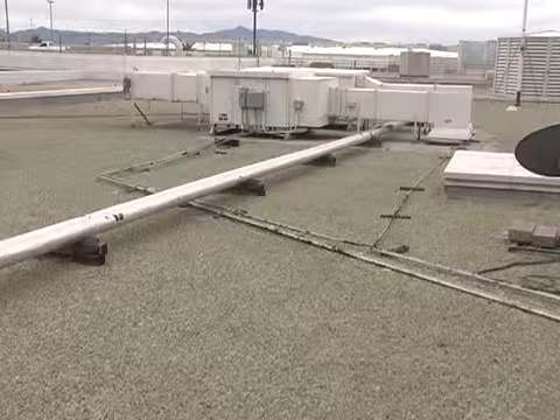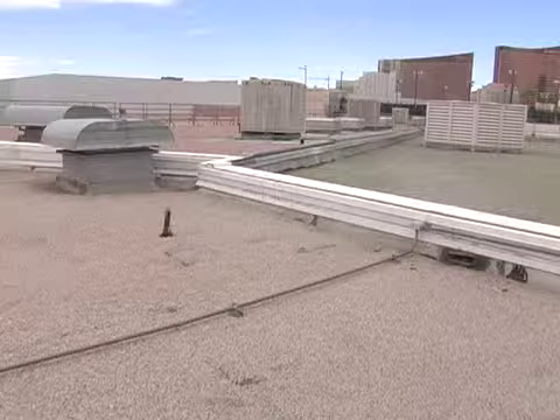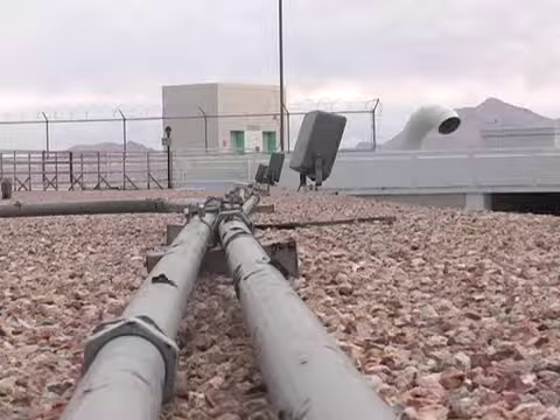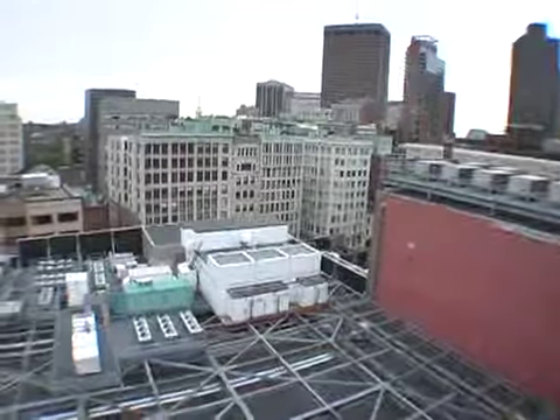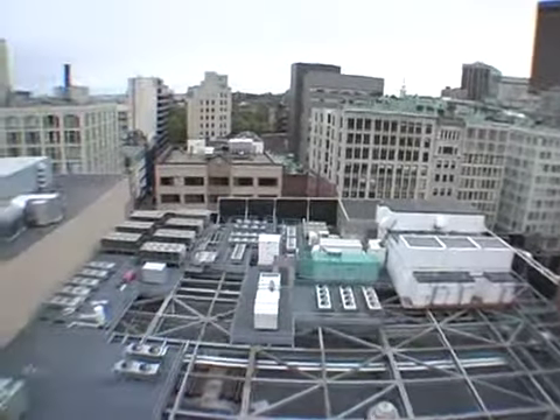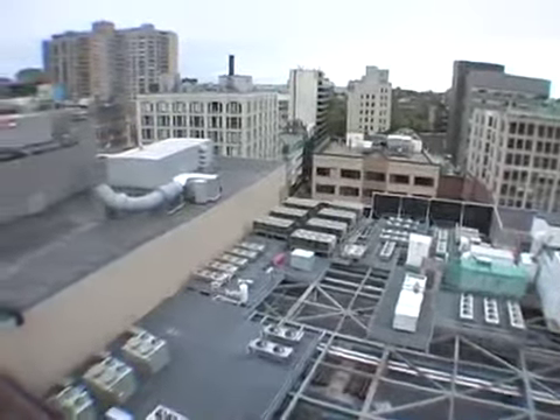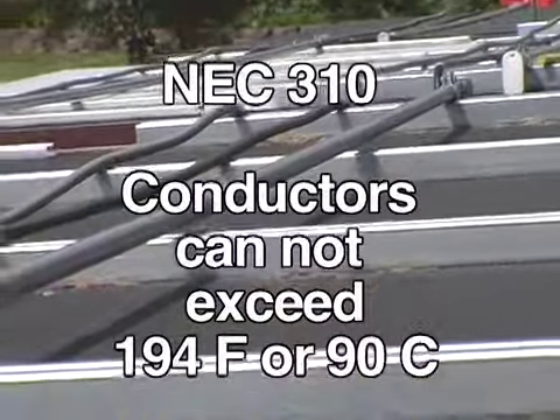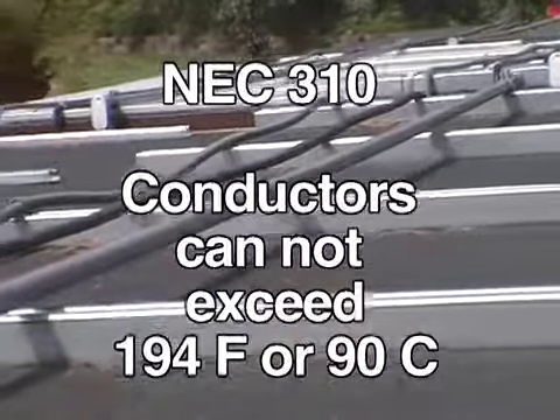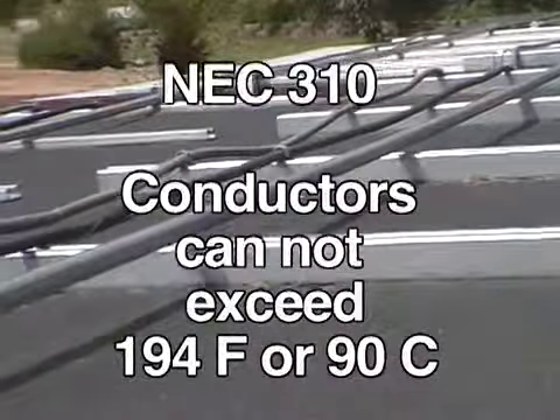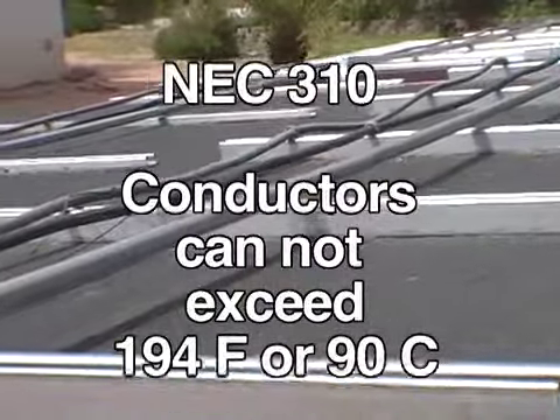They also told us they did not have all the necessary tools to apply the code with certainty, specifically NEC Article 310 and Table 310.16. These code sections require that conductors be adjusted for ambient temperatures so as not to exceed their rated ampacity when under load. In general, NEC 310 states that conductors cannot exceed the temperature that they are rated for, specifically 194°F or 90°C.